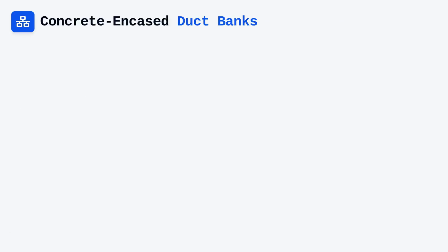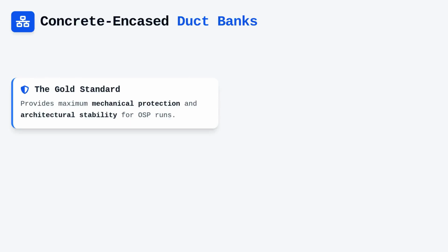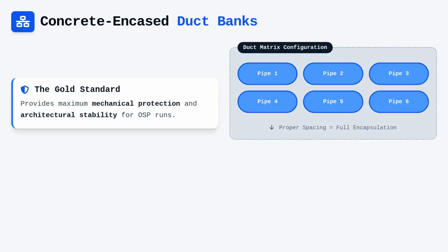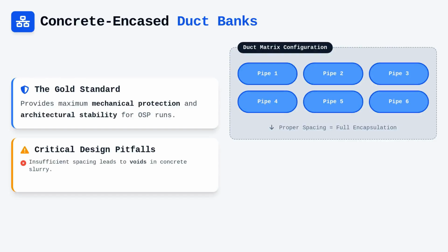Concrete encased duct banks represent the gold standard for secure OSP architecture, providing both mechanical protection and stability for the conduit runs. When designing the geometric configuration of these banks, we must look at the duct matrix, which refers to the physical arrangement of the conduits within the concrete envelope. A common error is failing to account for the necessary spacing between conduits, which is essential to ensure the concrete slurry properly encapsulates every pipe without leaving voids.